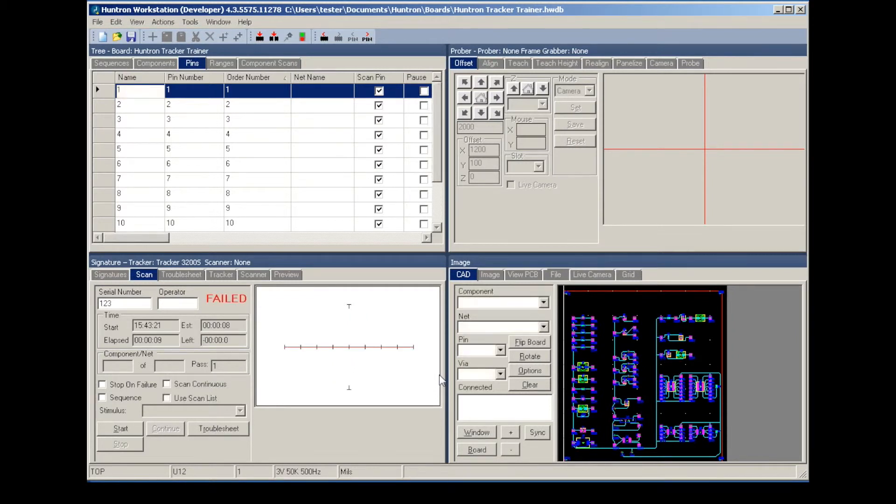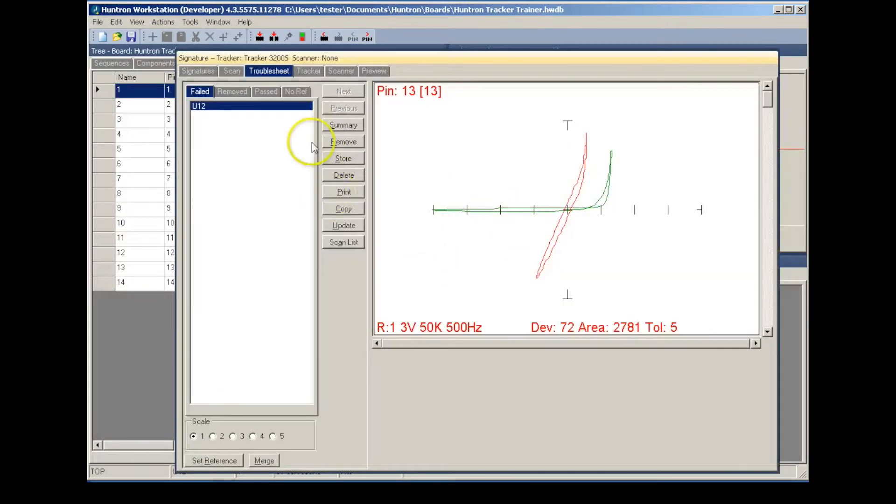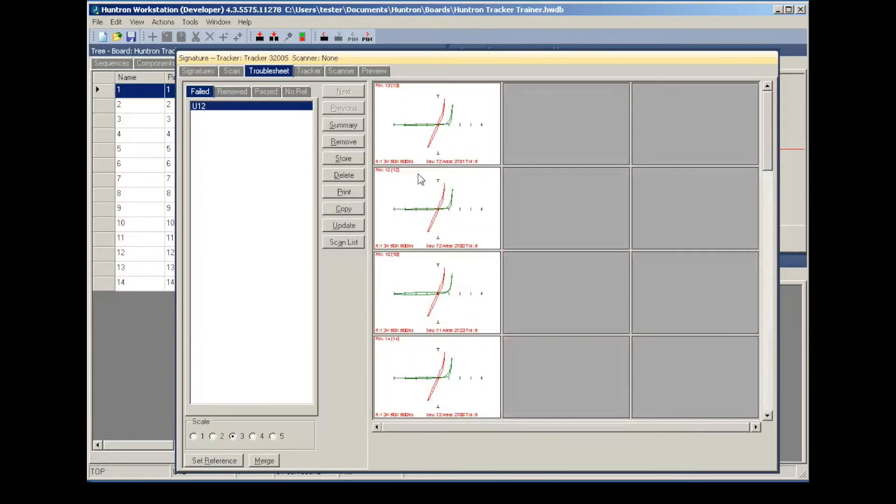Signatures of a suspect board are compared to stored good signatures and displayed on the screen for easy analysis. Failed pin signatures are shown in the workstation troublesheet in contrasting colors where green is the good signature and red is the failed signature.